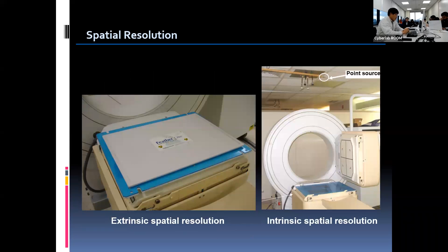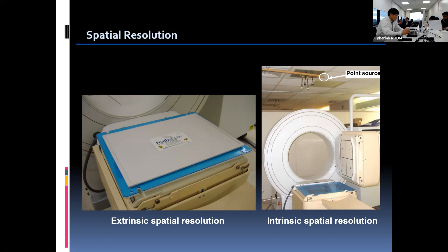The extrinsic resolution test is described in the left image. The four-quadrant bar phantom is placed right on the collimator mounted to the detector, and the cobalt sheet source covers on top of it. Resolution testing can also be done intrinsically without a collimator, using the technetium point source placed on the ceiling away from the detector, as described in the right image. In order to inspect over the entire detector with all different widths, the four-quadrant bar phantom is rotated 90 degrees, so different images are obtained for each detector.